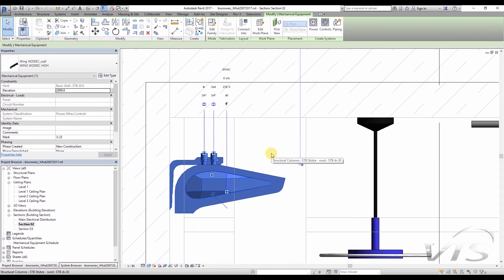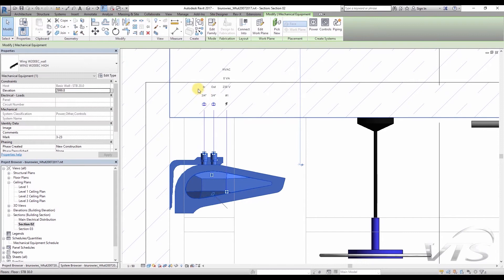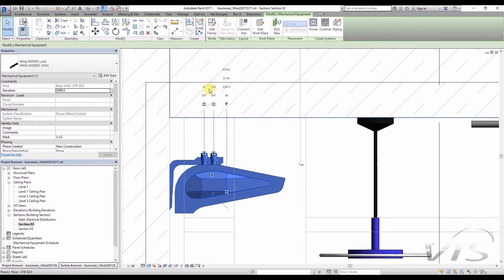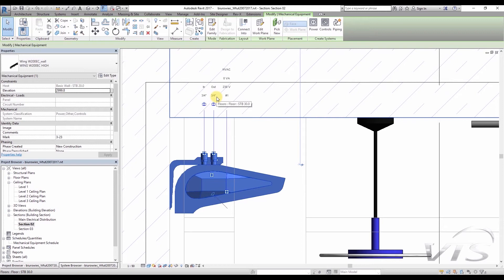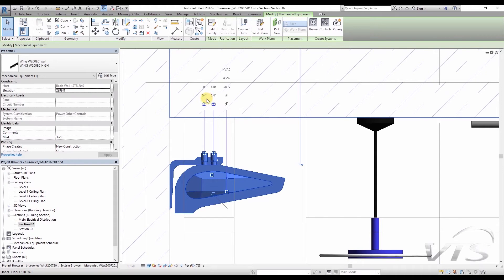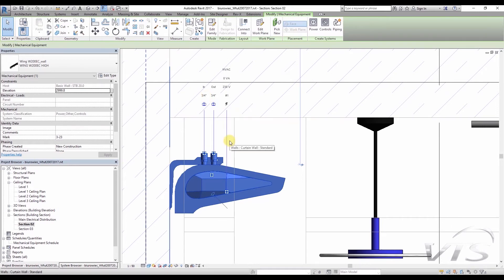On the left-hand side, we have the connector responsible for heating water, marked as in. On the right, we have out information, which means that this connector is responsible for the heating water return. Additionally, it is easy to note that the diameter of 3/4 of an inch has been defined for specific connectors. Thanks to that information, the software will be able to automatically select the diameter of the water supplying pipe.